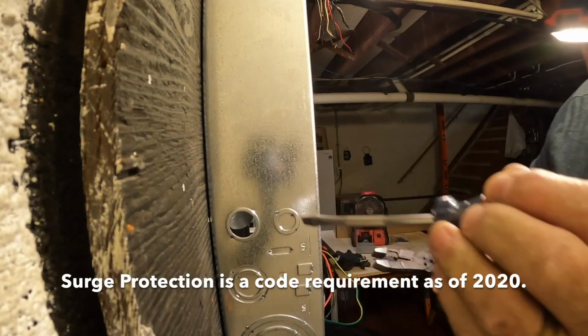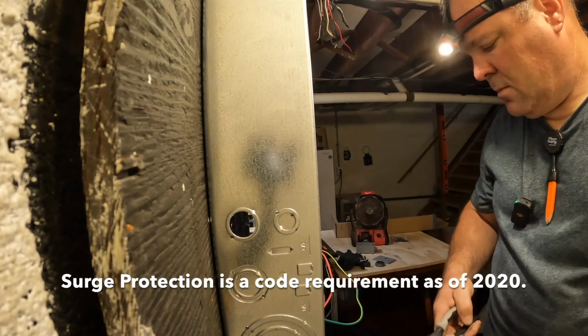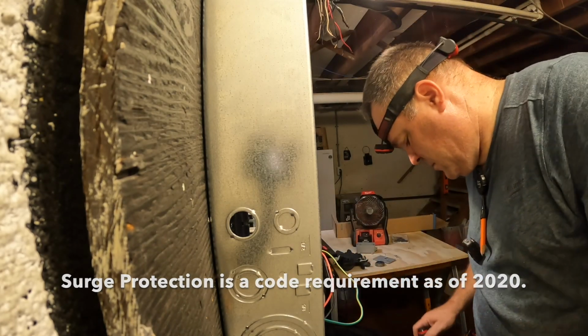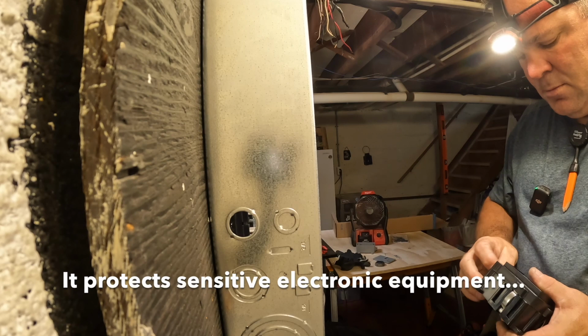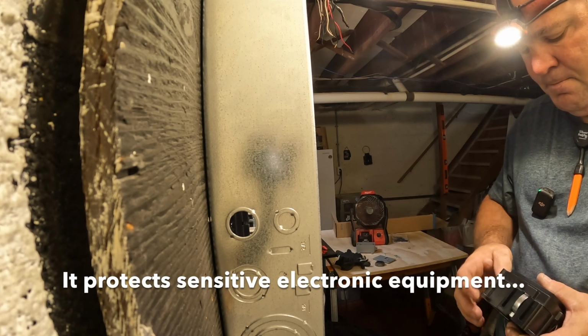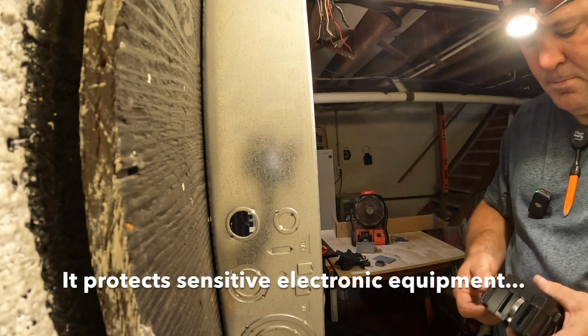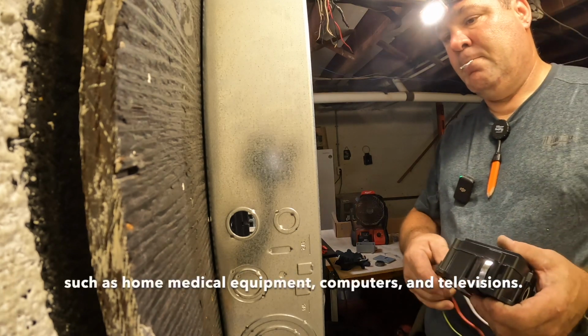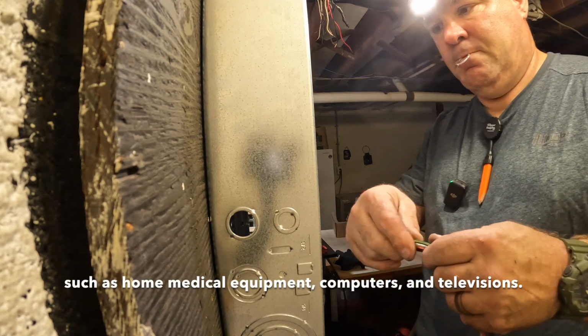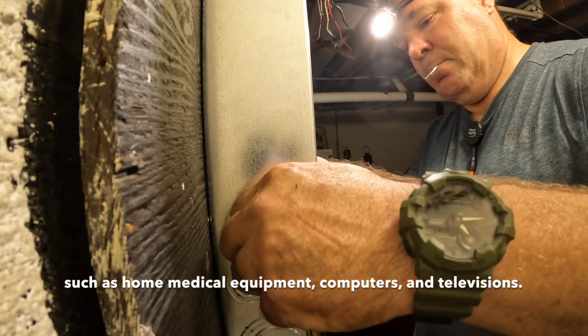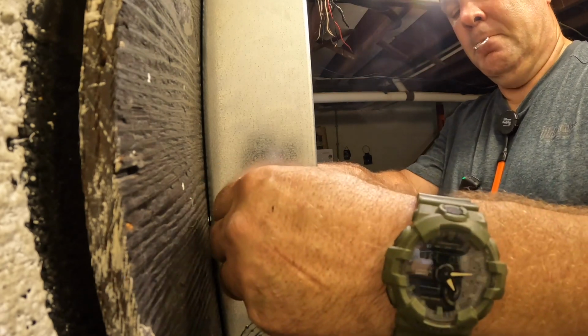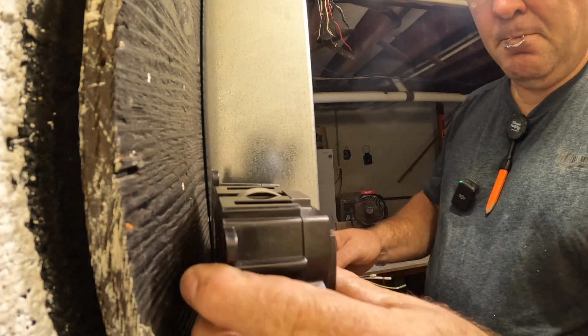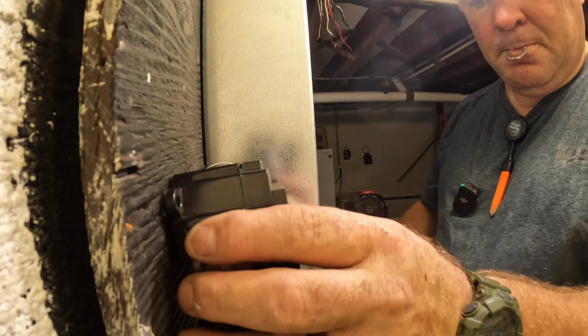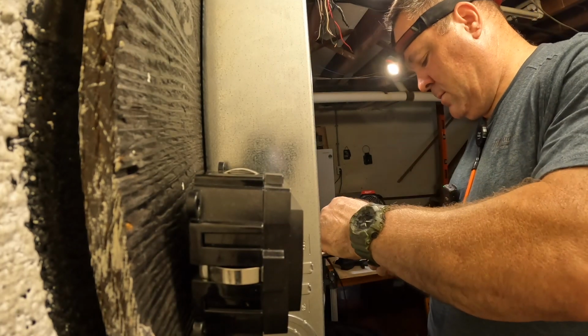So even when you're panel upgrading, you still have to put in a whole house surge protection device. It's required by section 230.85, I believe, is the code. And so anytime you upgrade a panel only, we have to put the whole house surge protection, and in New Jersey here, we have to update the grounding electrode system, which you'll see later in this video.